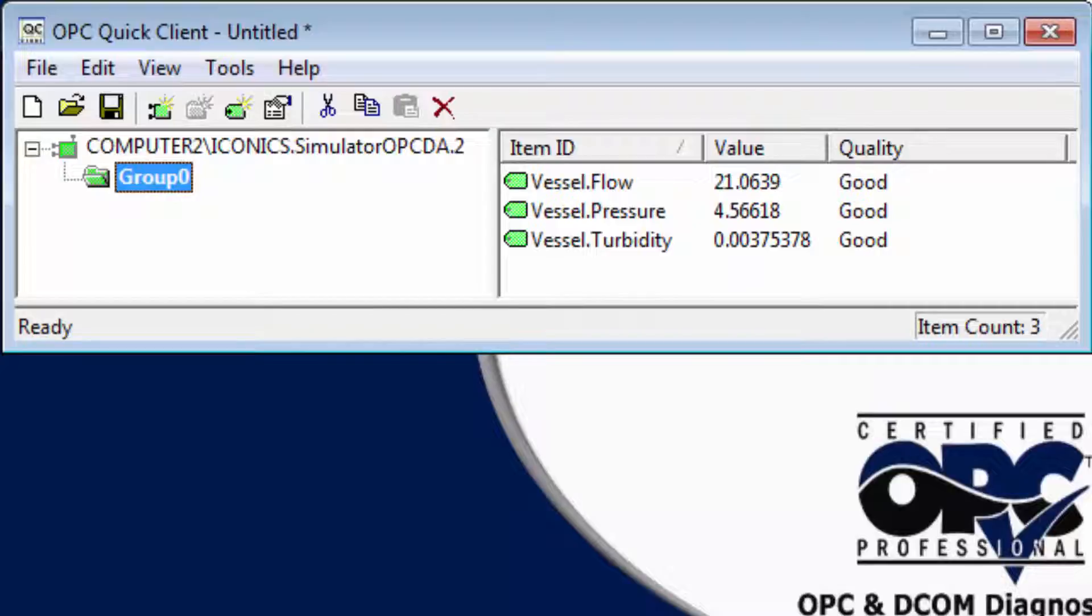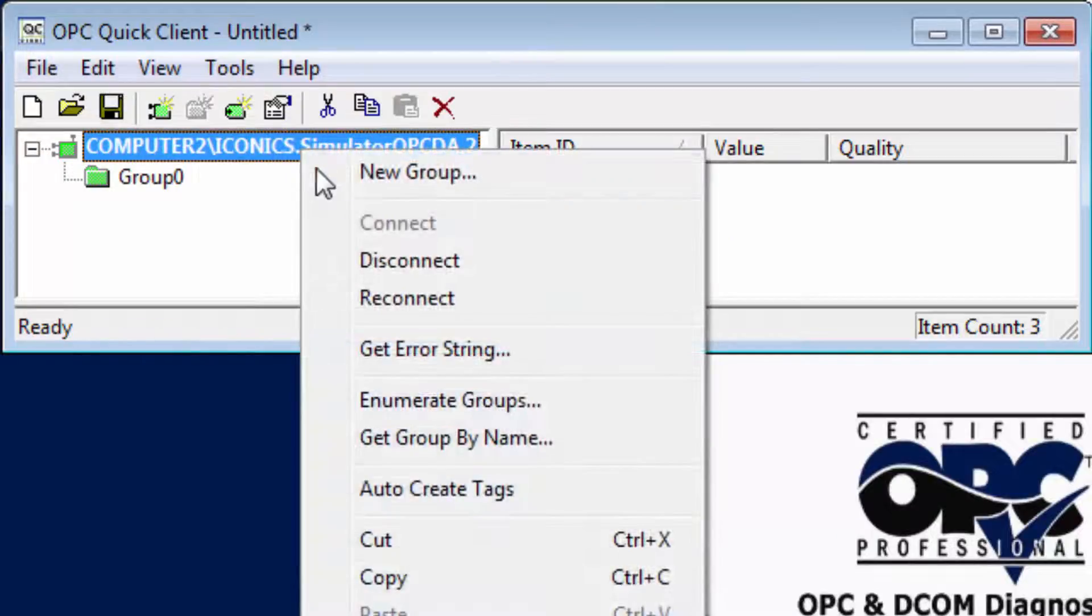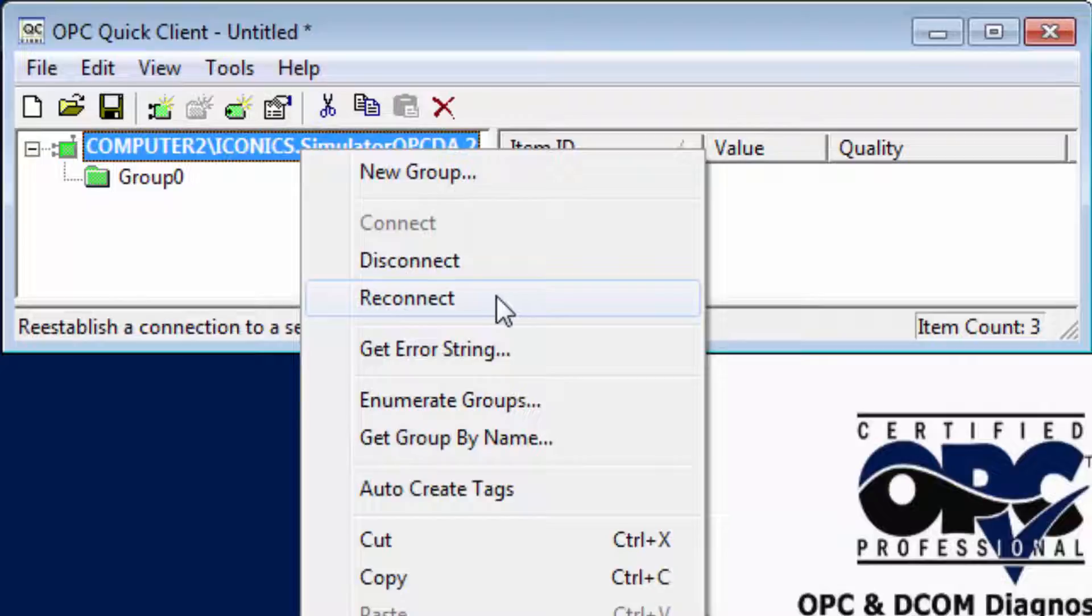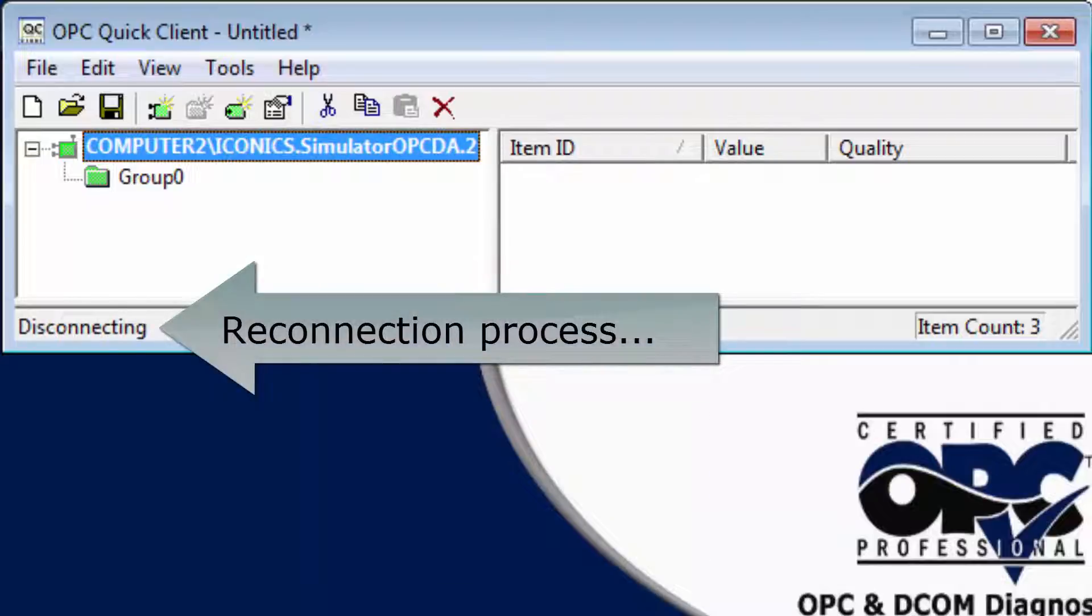So OPC Quick Client still believes it is connected to the OPC server. To receive updates again, I must manually reconnect to the OPC server. Many OPC client applications behave this way when they lose connection due to computer restarts, OPC server crashes, or network disconnections.